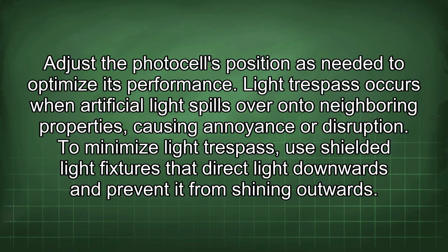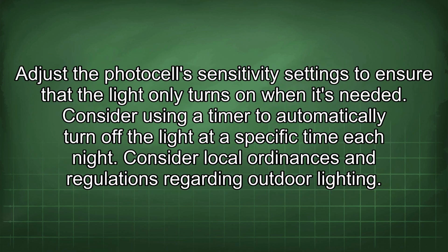Light trespass occurs when artificial light spills over onto neighboring properties, causing annoyance or disruption. To minimize light trespass, use shielded light fixtures that direct light downwards and prevent it from shining outwards. Adjust the photocell sensitivity settings to ensure that the light only turns on when it's needed. Consider using a timer to automatically turn off the light at a specific time each night.